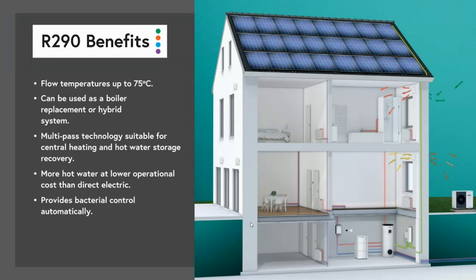With those sort of temperatures, the existing system is a high temperature design, and the R290 heat pump can power that system to a degree. And why I say that is 75 degrees doesn't give you very high efficiency. We would typically run that system at about 65 degrees. So when we do replace a boiler, we do need to be a bit careful that the system has enough safety factor in it that we could reduce the temperature by about 10 degrees and still get a good result.